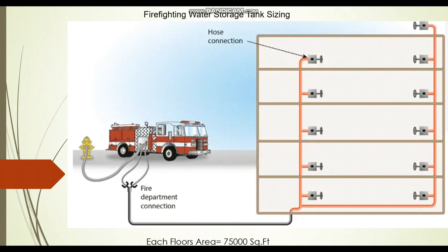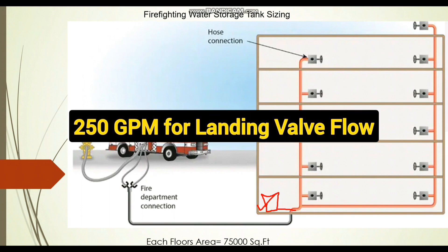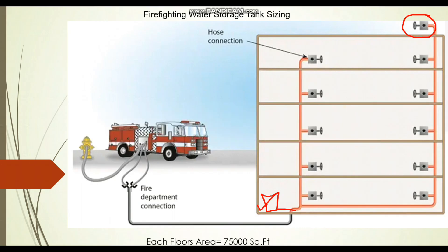In this project, let's assume we have a fire pump room with fire pumps supplying water to two risers. As per NFPA 14, we have to consider 250 GPM flow for each landing valve. For the last riser — also called the residual or remote riser, located farthest from the fire pump — even if you have 20, 30, or 50 landing valves, we consider a maximum of two landing valves. So 250 GPM plus 250 GPM gives a total of 500 GPM from the remote riser.